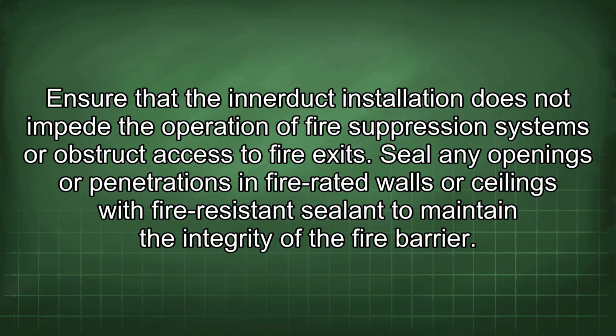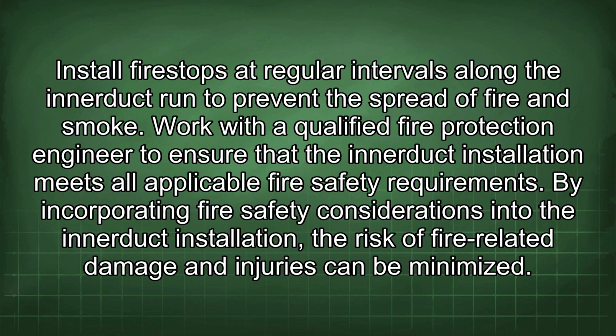Seal any openings or penetrations in fire-rated walls or ceilings with fire-resistant sealant to maintain the integrity of the fire barrier. Install fire stops at regular intervals along the Innerduct run to prevent the spread of fire and smoke. Work with a qualified fire protection engineer to ensure that the Innerduct installation meets all applicable fire safety requirements.